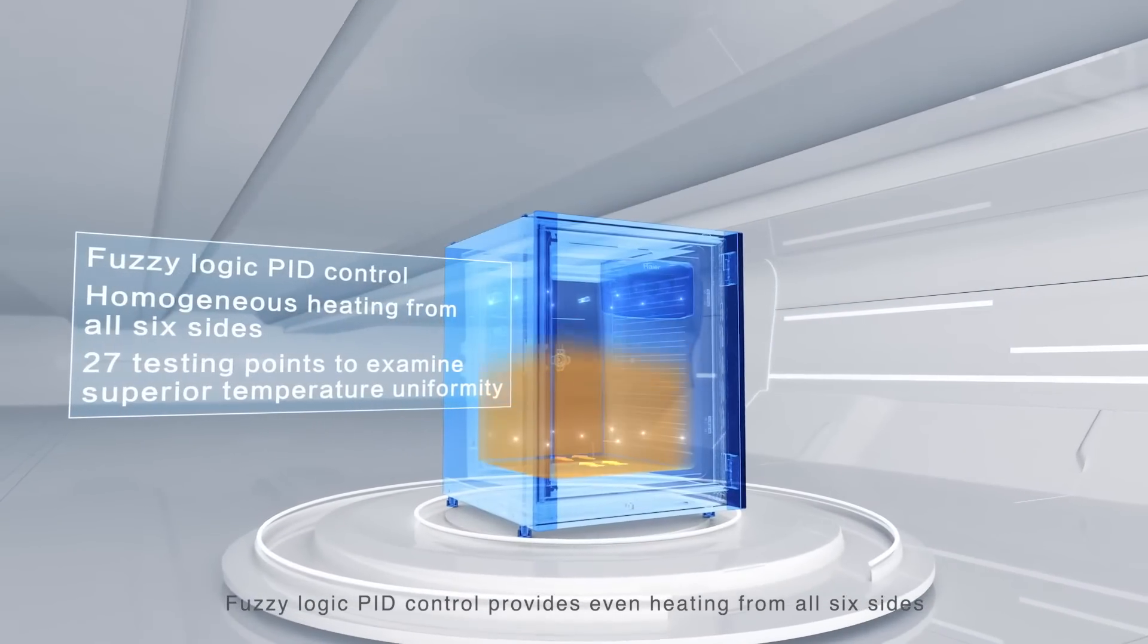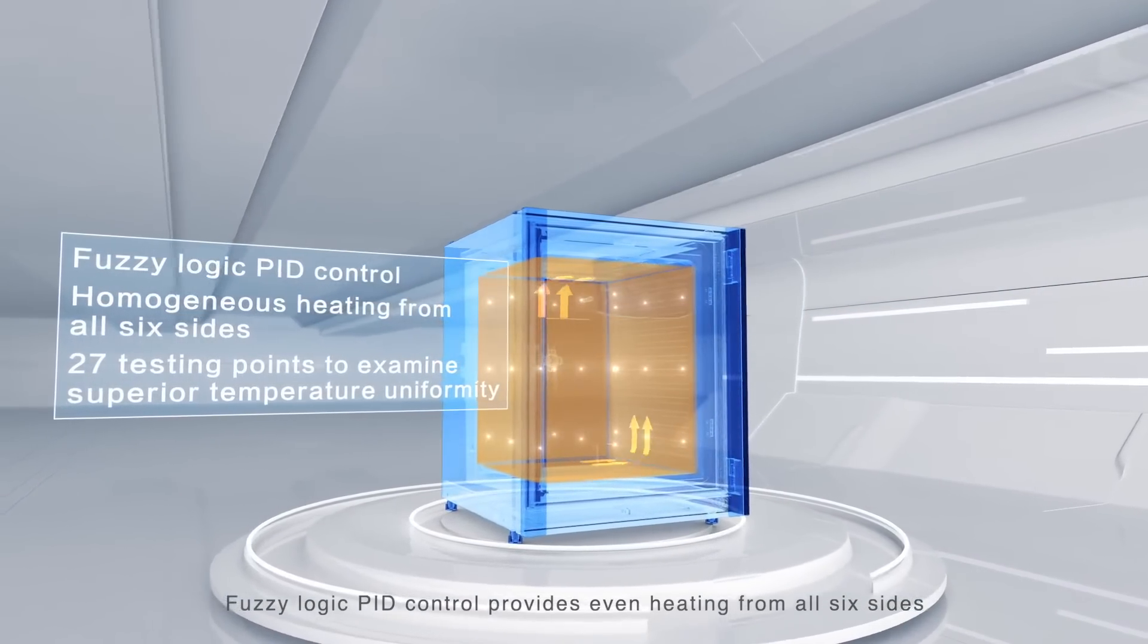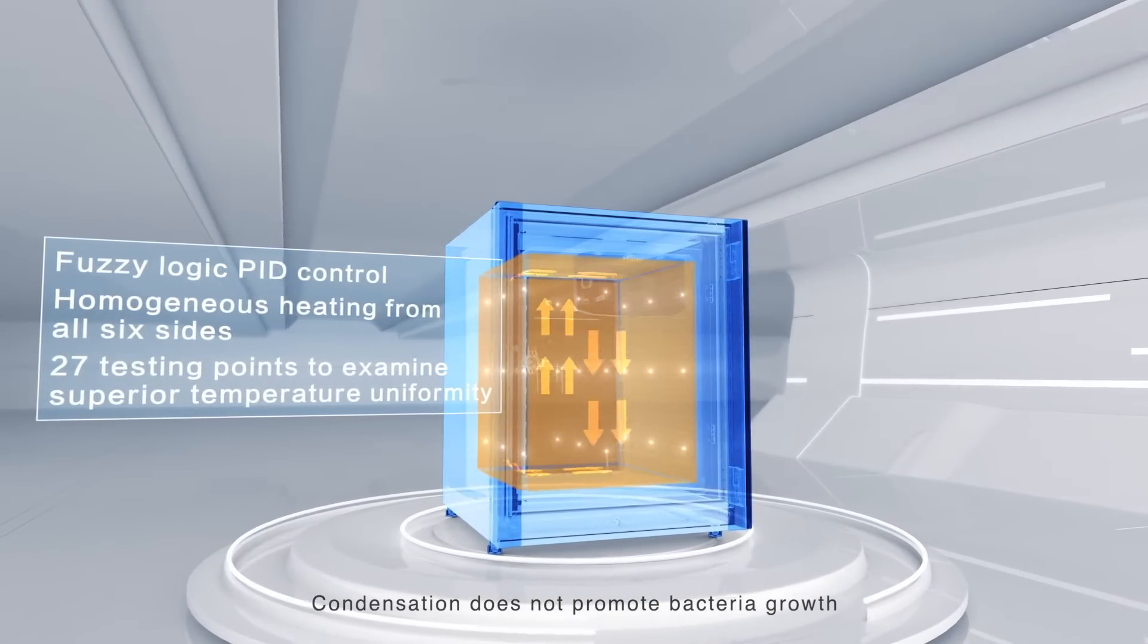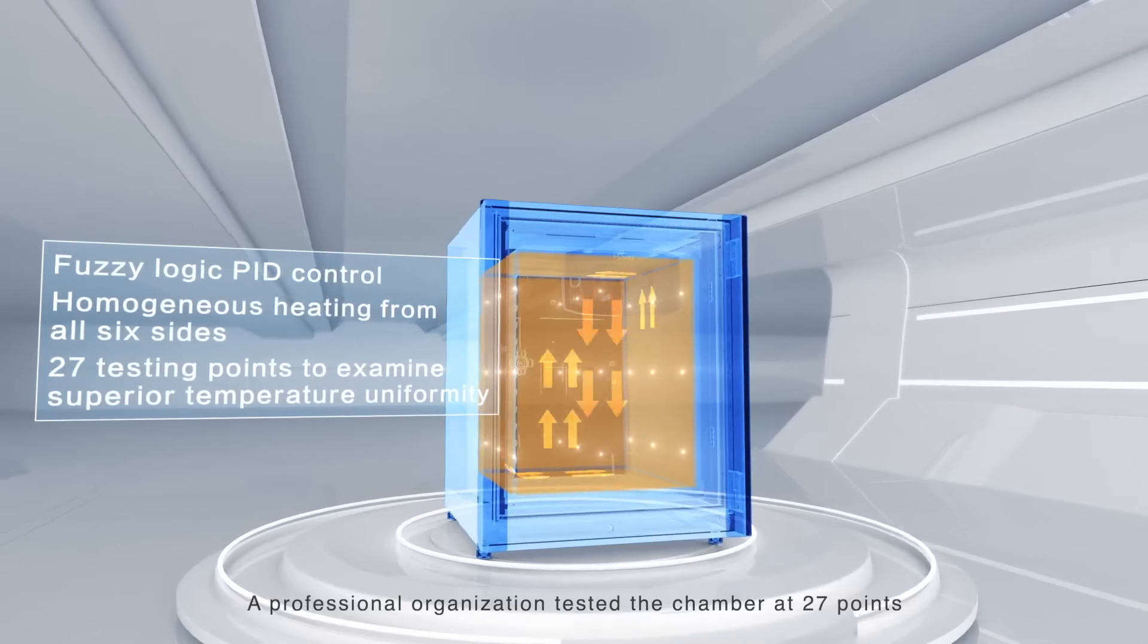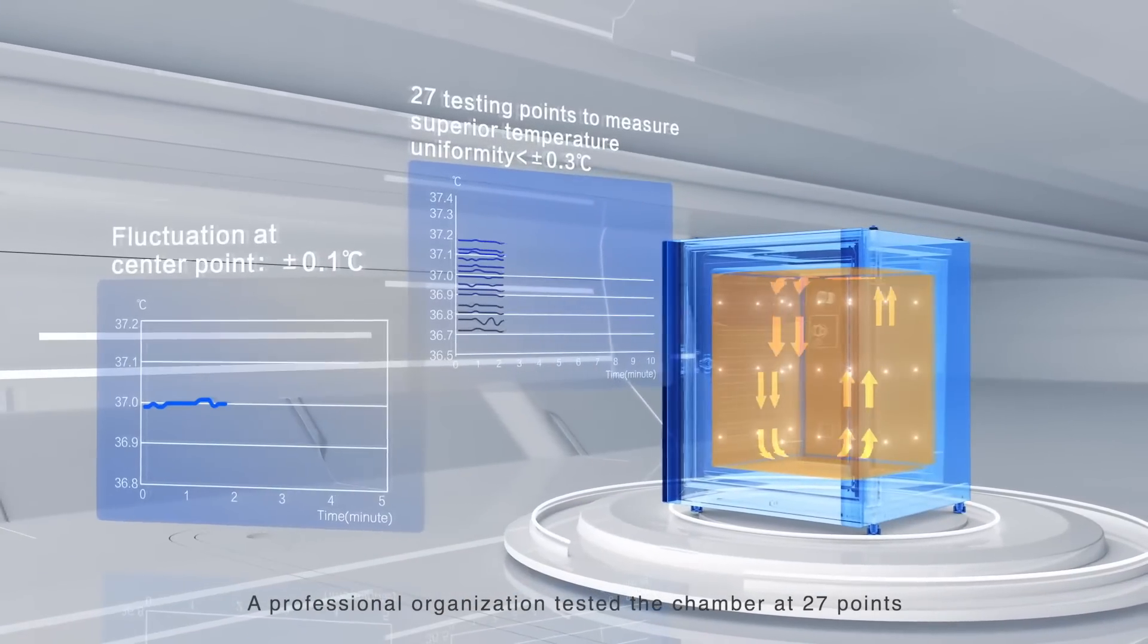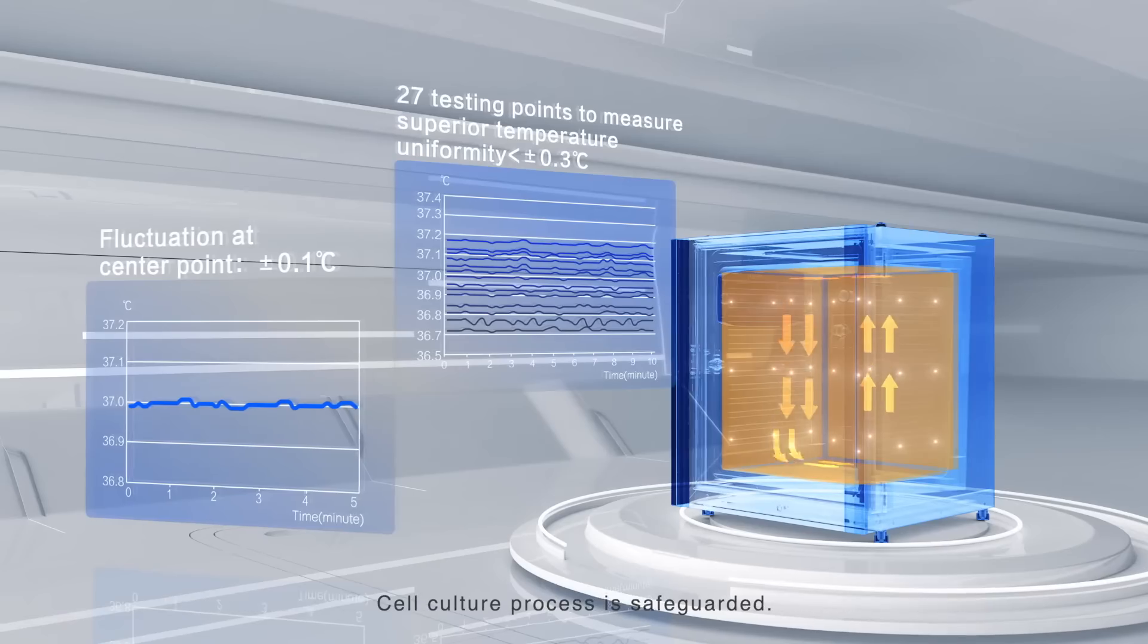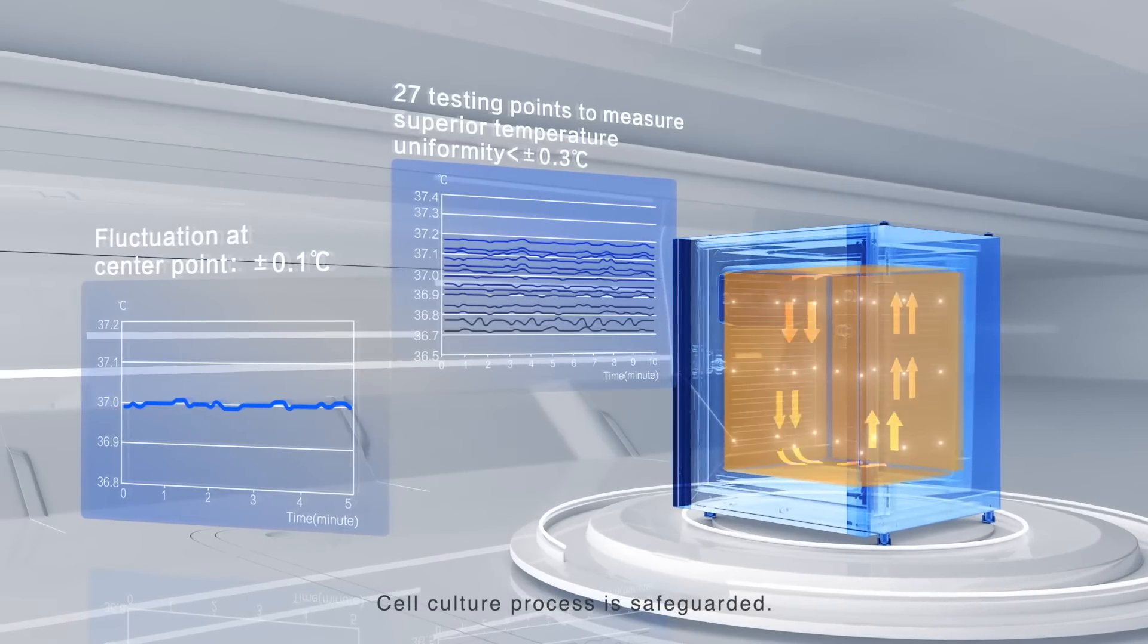Fuzzy Logic PID control provides even heating from all six sides. Condensation does not promote bacteria growth. A professional organization tested the chamber at 27 points to confirm superior temperature uniformity with precise temperature control. Cell culture process is safeguarded.